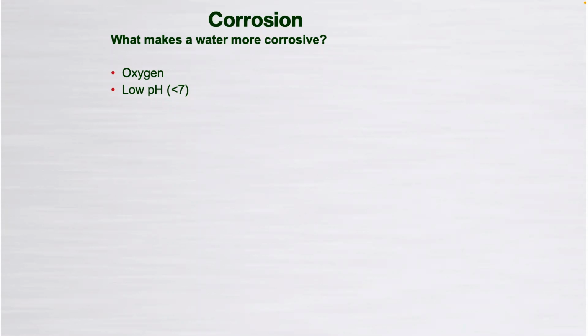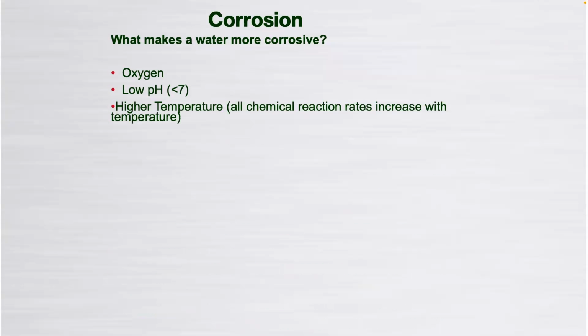So as a rule of thumb, it's 7. I mean, 7.2 is neutral, but we say 7 is neutral, and 7 up to 8.5 is what we would call neutral in the water treatment industry. So if you've got aluminum, any kind of aluminum in the system, you want to be neutral pH. Alkaline isn't an issue thereafter, but anything sub 7, we class as low pH, and that will drive corrosion.